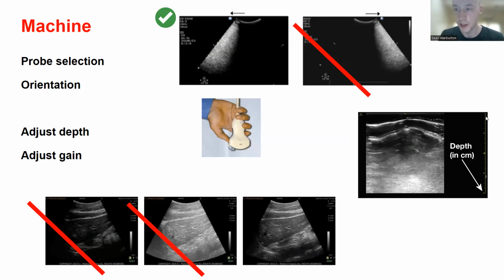So you can see on the right side of the screen, remember this is superficial to deep, it goes all the way down to 4 centimeters, and you've got depth marking. So this is about 2 centimeters. You can adjust the depth on your machine. So you could have it all the way down to 10 centimeters. But if your target is in the first 1 centimeter, that's 9 centimeters of wasted space. Your target is going to be very small. If you reduce the depth to 2 centimeters, suddenly your target's very big, and you want your target to be in the middle of the screen and nice and big.